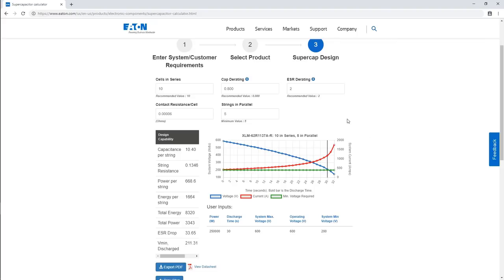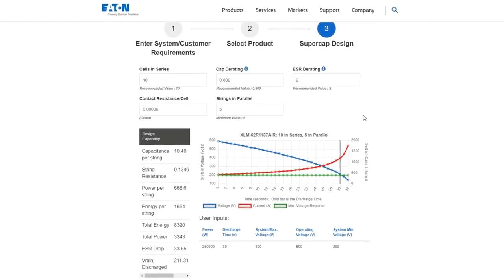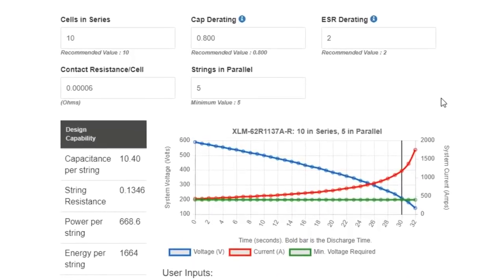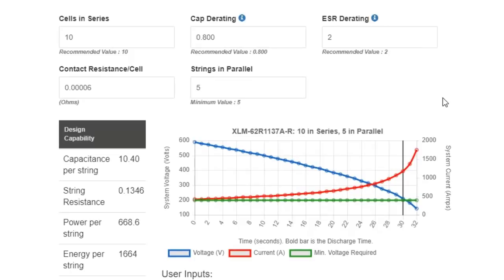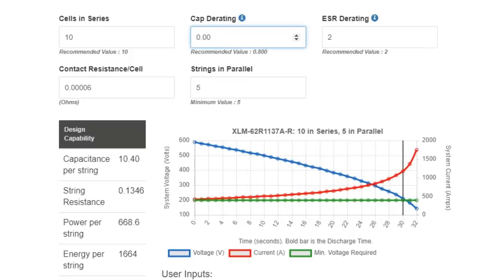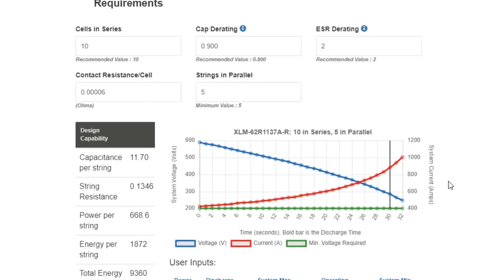If desiring to evaluate different end-of-life conditions, I can easily modify the supercap derating factor from 0.8 to 0.9 to optimally size supercapacitors. In doing so, you can see the changes in the discharge curve occur in real time to illustrate the performance of the supercapacitor system throughout its lifetime.